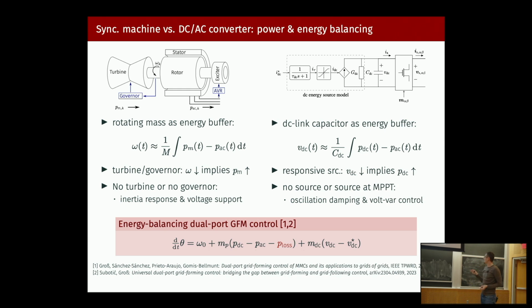To make our life a bit easier in terms of control, you see here this is nominal frequency. So basically I'm saying frequency of the converter should be nominal frequency plus a term that depends on the DC voltage deviation. Something nice here that comes in useful when you do a theoretical analysis of this is you can also use the power imbalance between the two terminals.